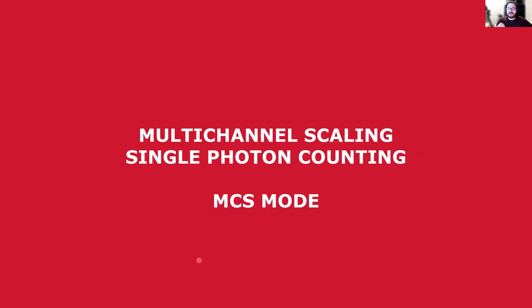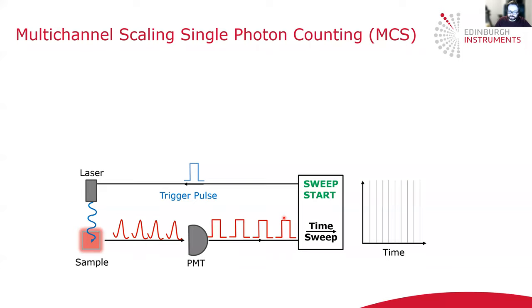The solution is to use a complementary measurement mode in the FLS1000 called multi-channel scaling single photon counting, or MCS mode for short. The basic layout of MCS mode is quite similar to TCSPC — we have counting electronics, a laser, a sample, and a detector. The difference is that this time the timing electronics trigger the laser rather than vice versa. So the timing electronics send a trigger to the laser telling it to fire. The laser fires and excites the sample. The sample emits multiple photons, which are detected by the detector and converted into electrical pulses, which are then recorded using the timing electronics.